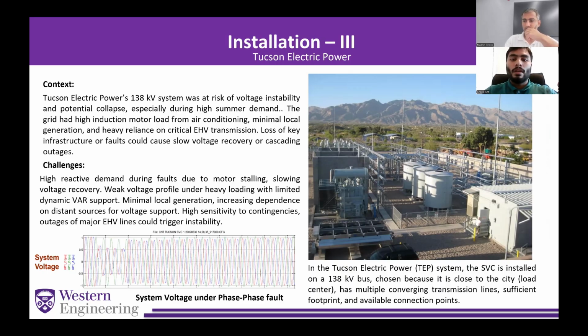Yeah, so our third case study is an installation in Tucson Electric Power. Due to the high load in peak season, that is summer, the system became highly unstable. I'm talking about voltage stability, and this instability was a threat of collapse of the system, because the voltage used to go below 0.9 per unit, which is not in the operating range. It was due to the high reactive demand during faults due to motor stalling and slow voltage recovery. So to cater to this problem, they installed an SVC. Can you go to the next slide, please?